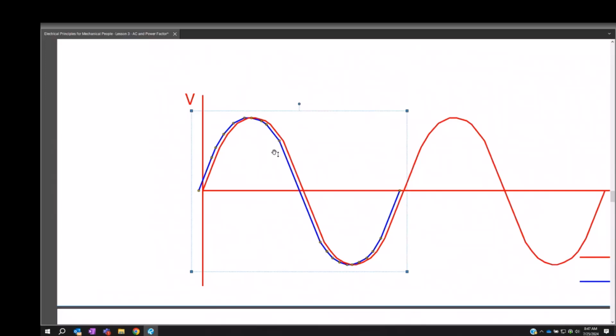However, I can counteract the reactive power that is required to bring this back to what's called unity power factor, a power factor of 1. Doing a cap bank can completely make it like a one-to-one. A power factor of 1.